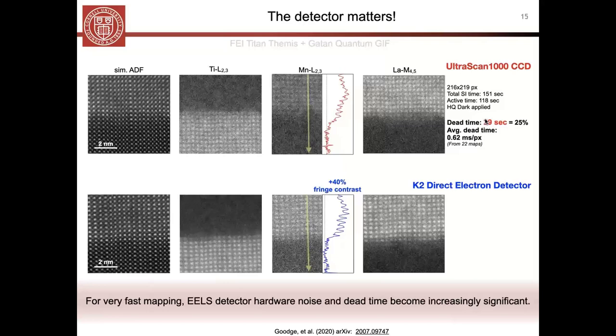That's the total active time of the exposure. But then you can also look at when it starts and when it really ends, which is the total time. The difference between the total time and the active time gives you what we call the dead time. This is time that's passing, and if you're under cryogenic conditions, it's time that your sample is drifting but not contributing to any increase in signal.